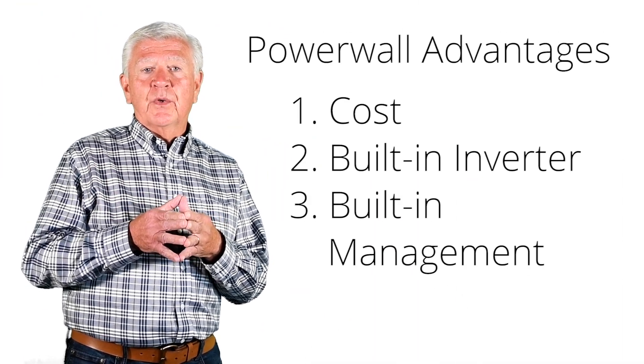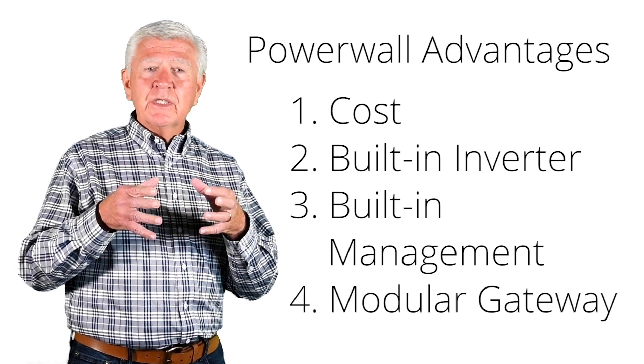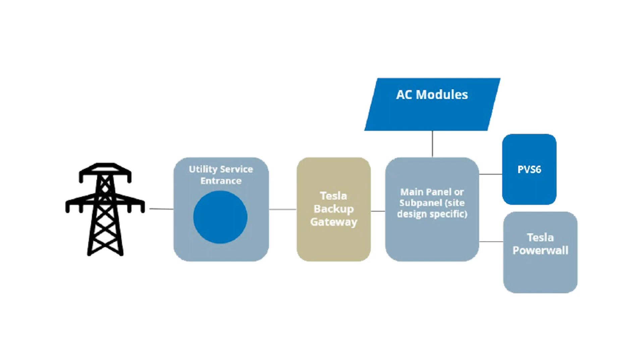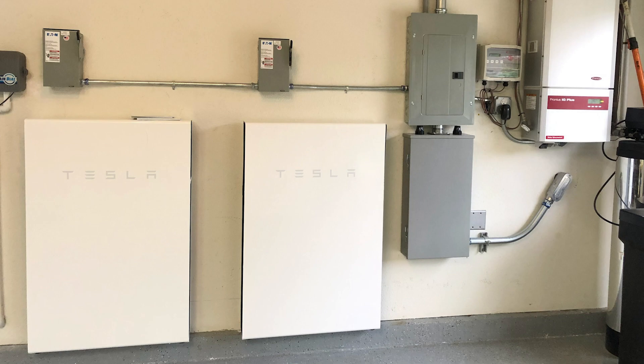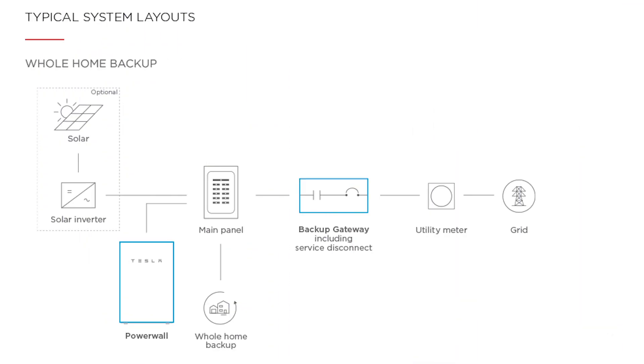Another reason why the Tesla Powerwall is a great component is because they have what's called a modular gateway. In order to do emergency backup power for your home, there has to be a separate component that isolates your backup circuit breaker box from your primary circuit breaker box, because the utility is hooked to your primary box. The battery powers a separate set of circuit breakers for your home. That gateway hooks up to the Powerwall very easily, making for a much easier installation and quick permitting. All these components are meant to go together, which is a really big plus for emergency backup power.